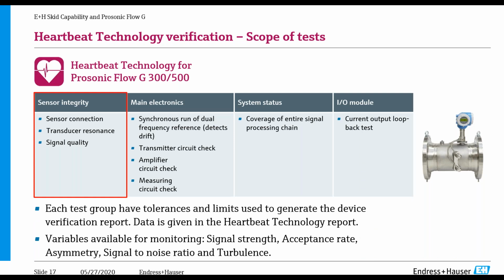I mentioned quite a few times about Heartbeat Technology. One of the most important things about Heartbeat is checking all the diagnostics, but what we have inside is our critical measurement value is coming from time, okay? And we use a quartz crystal for that. What we've done is integrated a second quartz into the transmitter. And what we use this second quartz for is to see if there's any drift in the main reference quartz for the flow value. So we're able to see if the meter's being affected at all over time, if it's drifting or not, and we're doing checks on that.